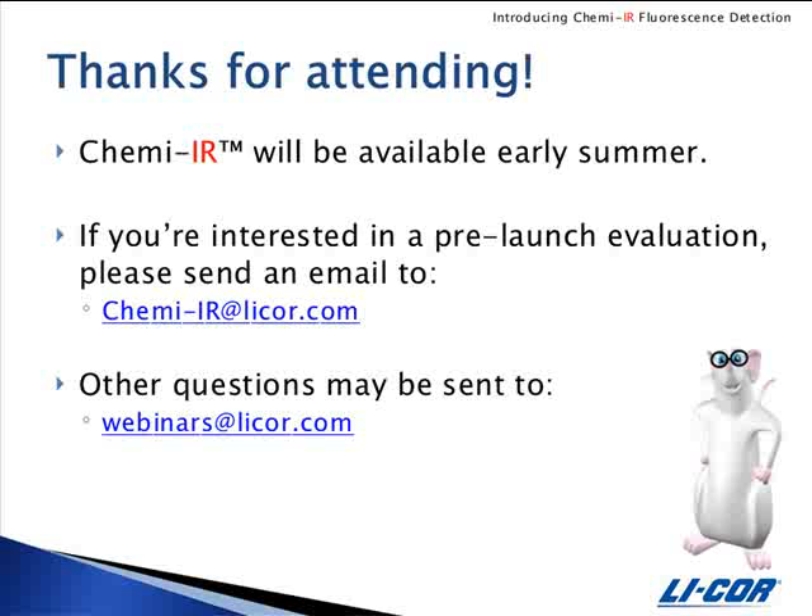How do I know what intensity setting to use for scanning Chemi-IR blots? For Chemi-IR detection, you will use the membrane preset and I would recommend scanning in the 800 channel only, starting with an intensity of 6. You may need to optimize that according to how your image comes out, but I would recommend starting with an intensity of 6.